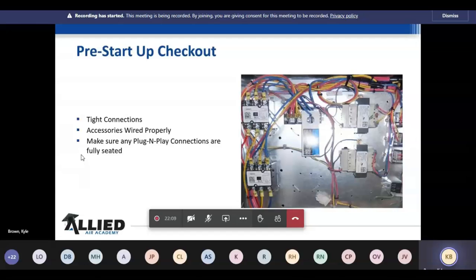So while we want to get our mechanical contractors and our technicians that are going out to always pay attention to this, even when they go do cleaning checks, and sometimes these units get run hard, they need to check this each and every time, even the plug and play connections. If you'll notice at the very bottom of this box, right down here, there's a plug just laying out. The question comes in all the time, is something missing on the unit? What was that plug for? Why is it like that? These units are pre-wired for a lot of accessories, and you'll see some other wiring issues I want to show you in just a moment.